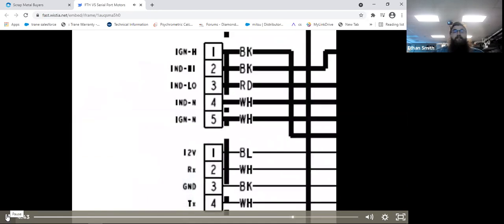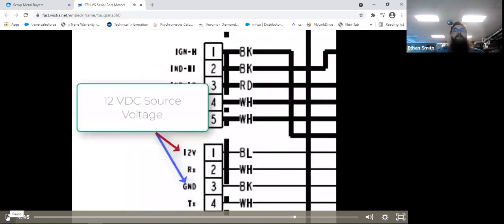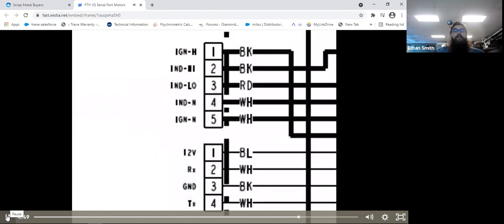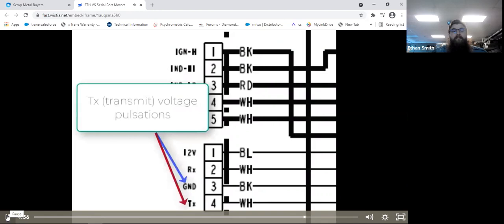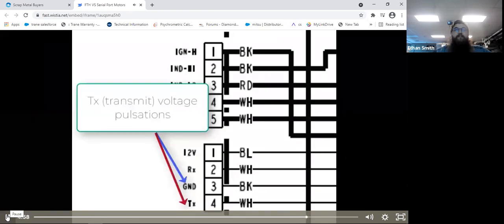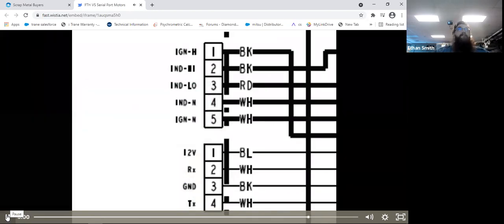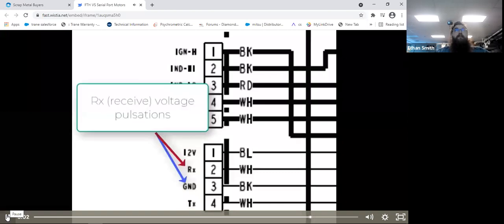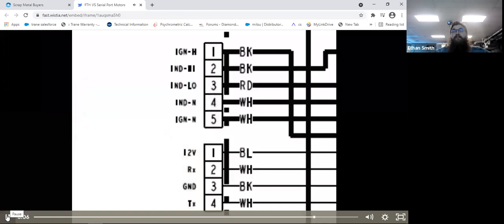If the motor does run, I will continue the diagnostics to make sure I have 12 volt source DC voltage on the control board. If I do not have 12 volt source, I'm going to replace the control board. If I do have a 12 volt source, I'm going to focus on the TX for transmit to make sure the board's sending voltage packets to the motor. If I see the pulsation, I'm going to move to the RX circuit, and I'm going to look for a slight drop in voltage from what I have from the source.